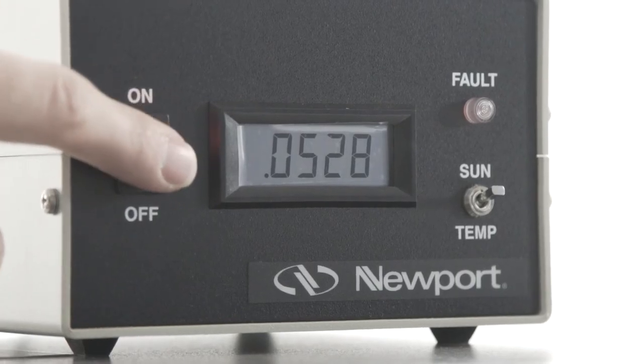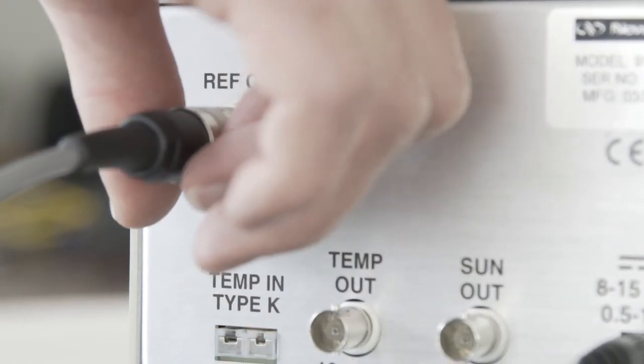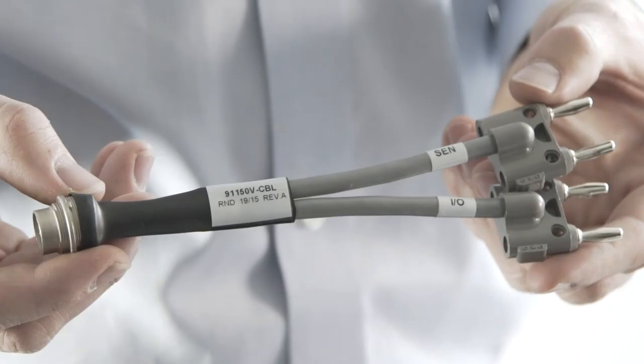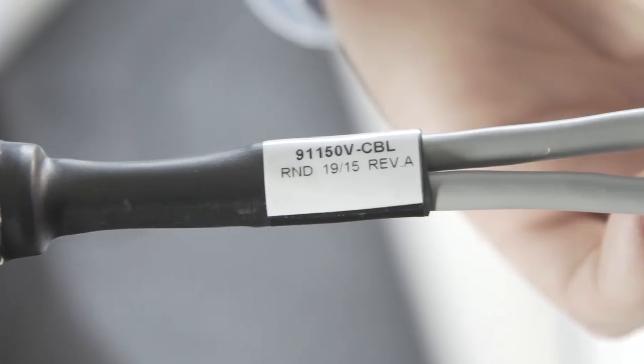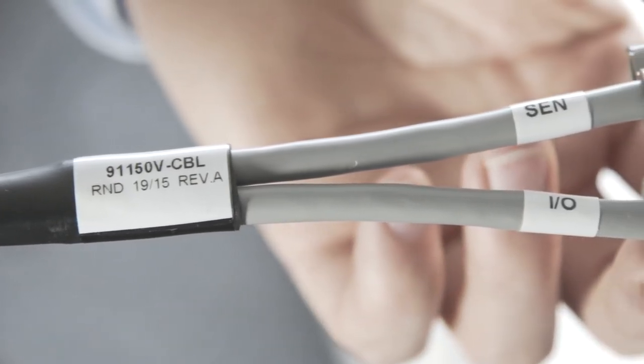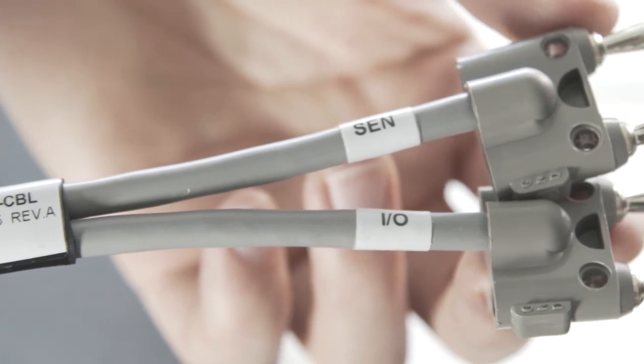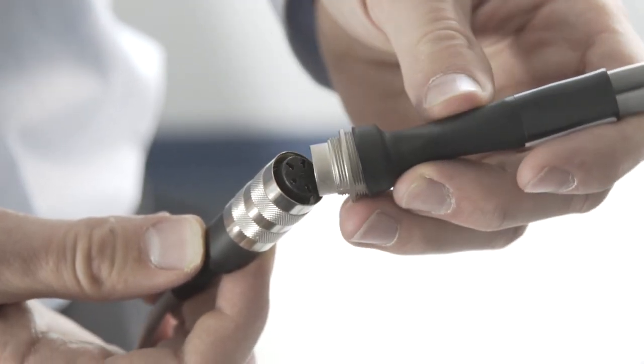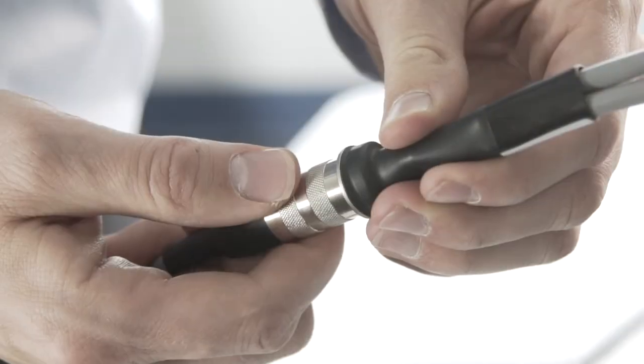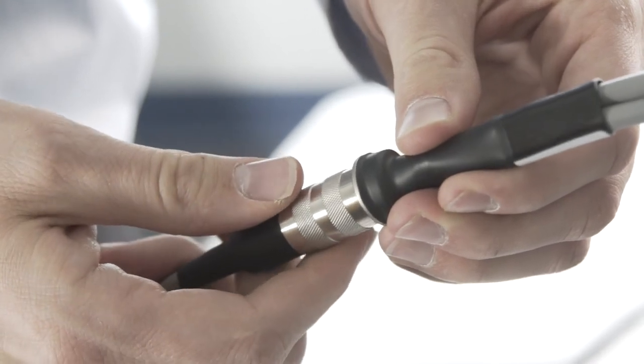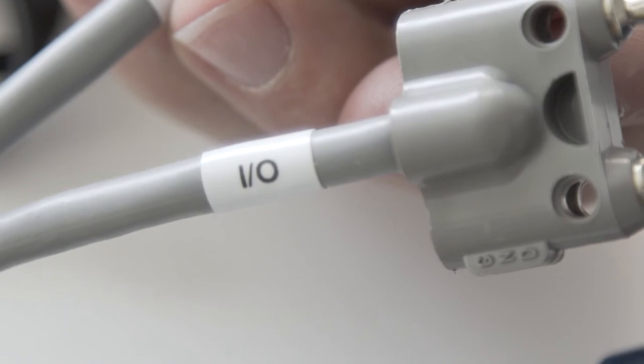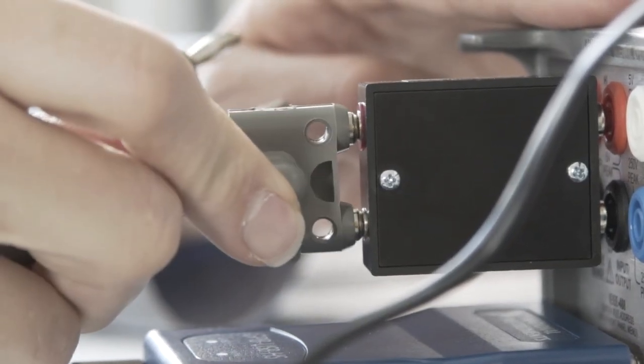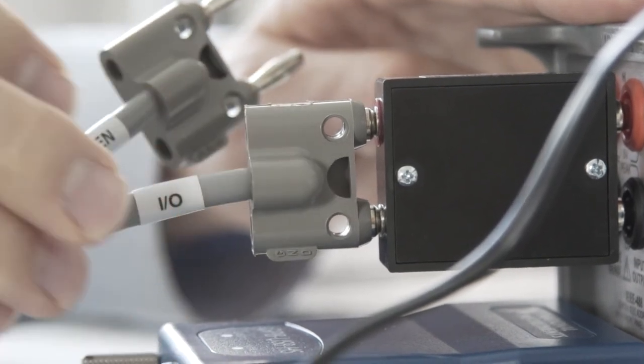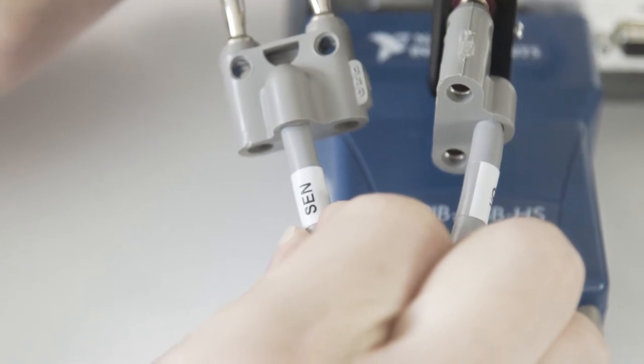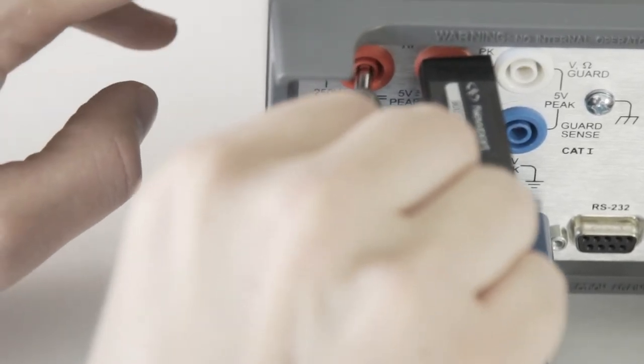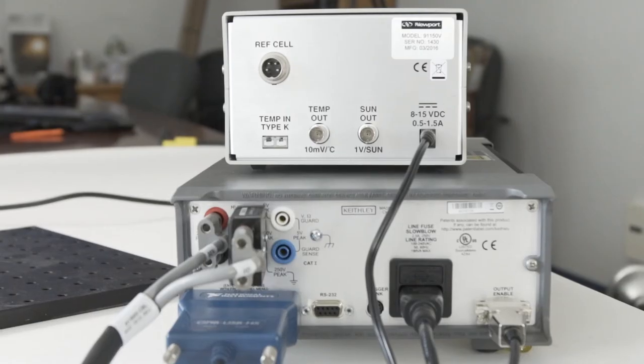Now we can replace the 91150V reference cell connections from its meter to the PVIV Keithley source meter. We use cable model 91150V-CBL provided with the cell. It's critical to connect the cell to the meter in the four-wire configuration. Without these sense connections made, we will receive erroneous results. That's all for the hardware setup.